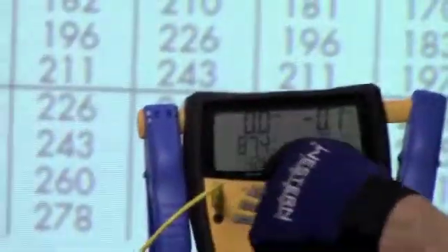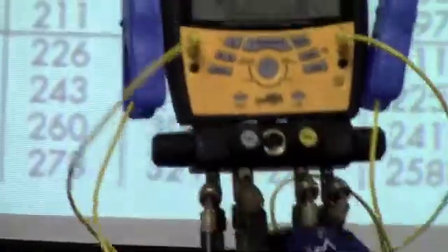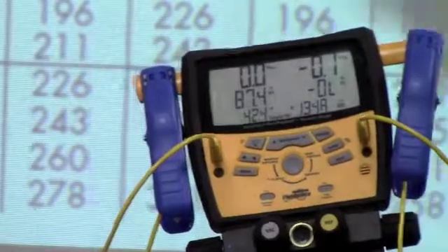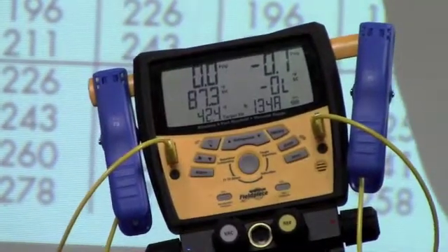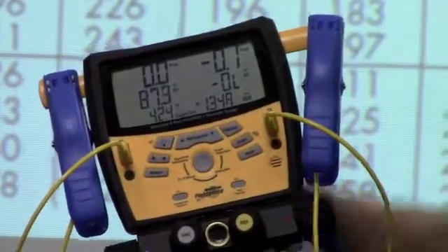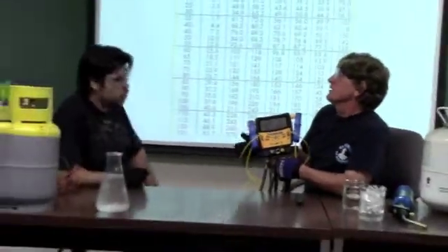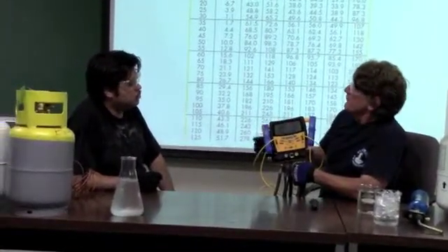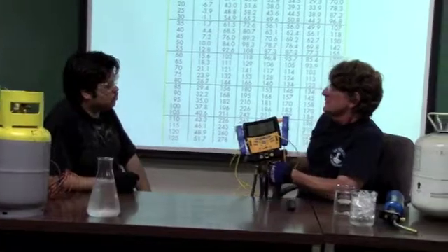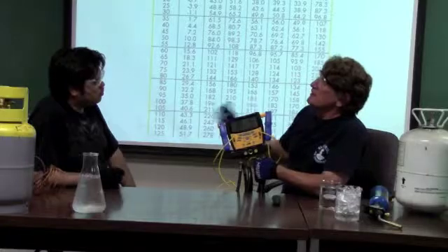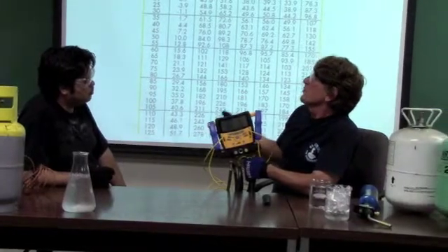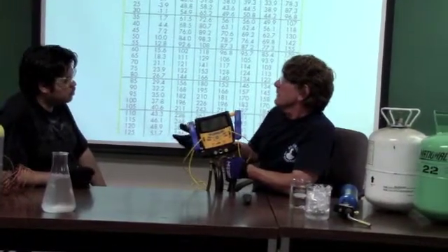These look a little better. These dudes have built in all these functions — they're digital displays, got some more knobs to turn. But in essence, internally into this device, it has this pressure-temperature chart built in. We've talked about getting saturation — that's our starting point. You can't do superheat or subcooling without first determining saturation. Once I've determined saturation, I need another temperature, like the leaving refrigerant temperature from the condenser or the leaving refrigerant temperature from the evaporator.